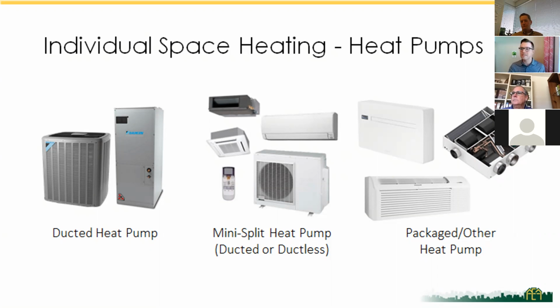We have a variety of different options. On the right-hand side, the packaged units tend to be the lower cost options, good for very small compact units like studios, maybe one bedrooms. The unit shown on the far right, broken open, is actually a combination heat pump and ventilation system—doing heat recovery, ventilation, and heating and cooling in a single box. That's a really exciting product category they've had in other countries for a long time, and it's starting to become available more widely in the US. It's a great opportunity to get a lot of efficiency out of your mechanical install and get two systems in one.